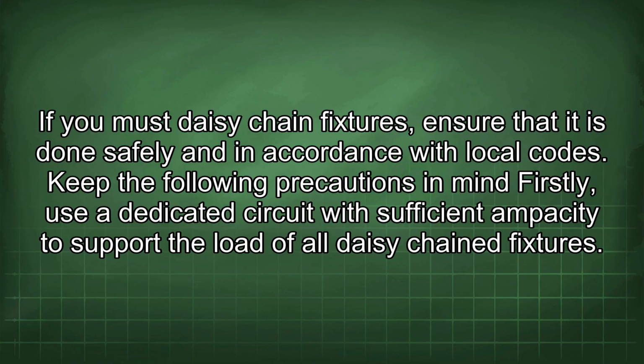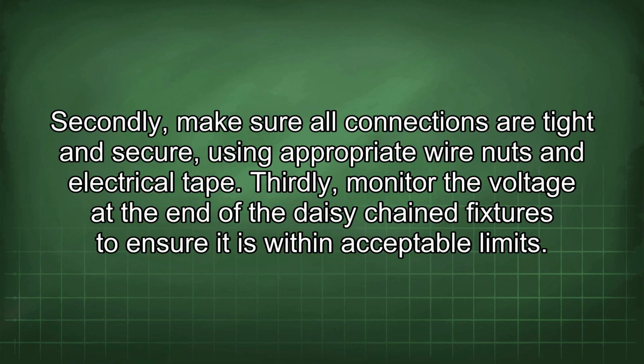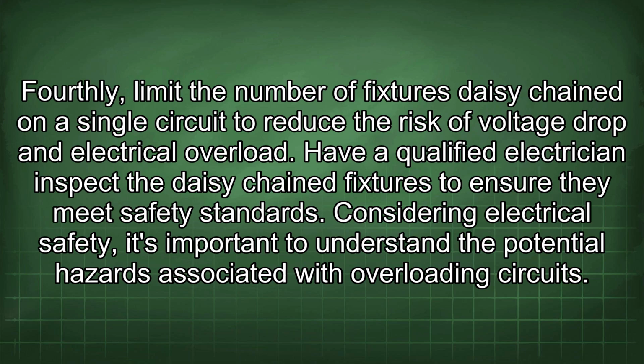Firstly, use a dedicated circuit with sufficient capacity to support the load of all daisy chain fixtures. Secondly, make sure all connections are tight and secure, using appropriate wire nuts and electrical tape. Thirdly, monitor the voltage at the end of the daisy chained fixtures to ensure it is within acceptable limits. Fourthly, limit the number of fixtures daisy chained on a single circuit to reduce the risk of voltage drop and electrical overload. Have a qualified electrician inspect the daisy chained fixtures to ensure they meet safety standards.